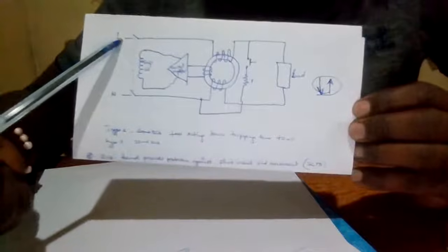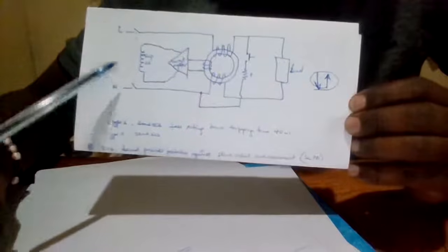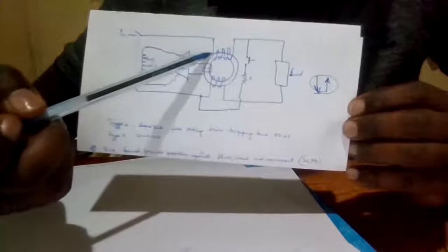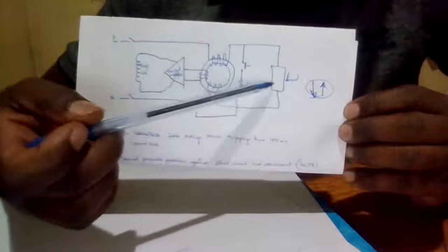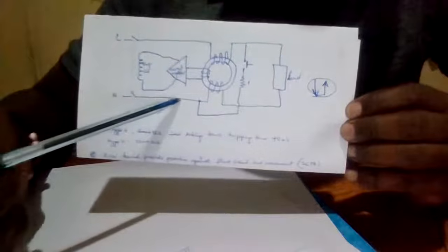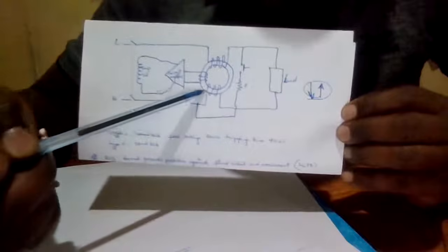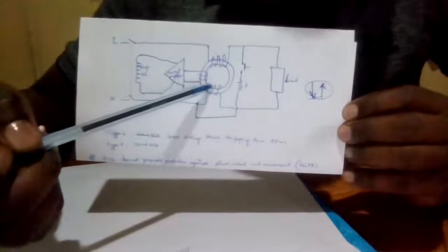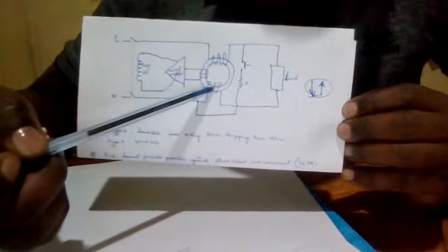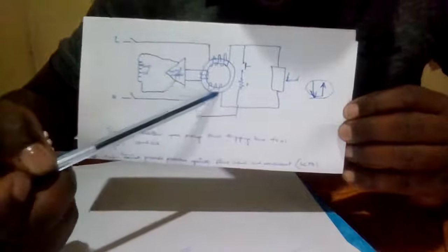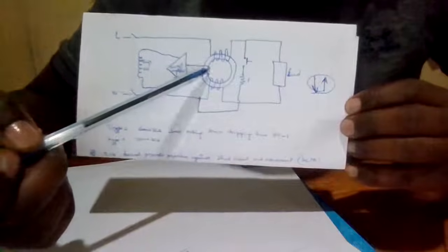So for this, if you can see very well, this is how it is arranged. We have a live wire and a neutral wire. The neutral comes and passes through the toroid and goes out to the load. Likewise, the live wire passes through the toroid with the same number of turns as the neutral, and then goes to the load. Now, if these two are equal, the resultant will be zero. That is the philosophy of how it is supposed to work.